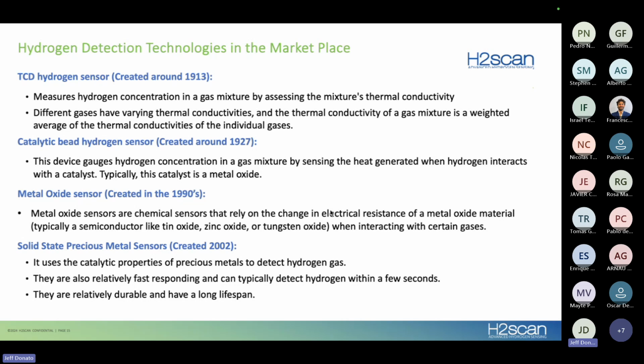And that's something you'll have to consider, whether it's right for your site or not. There's a very common one in vented battery rooms, the catalytic bead sensor, and a lot of you are probably most familiar with this. This device has been around since 1927, and it uses catalytic beads, and when hydrogen or any kind of gas interacts with the catalyst, the carbon layer over the bead, it heats up and causes a resistance change.